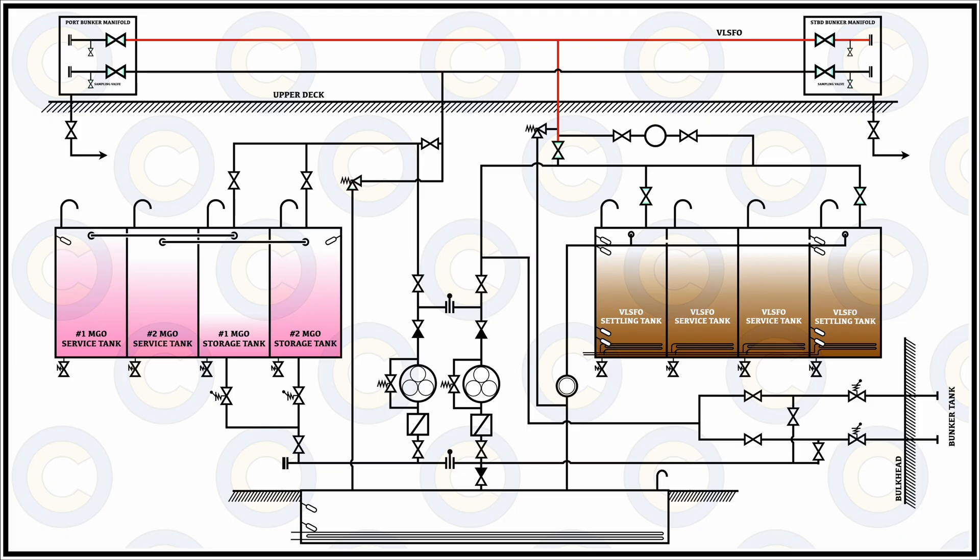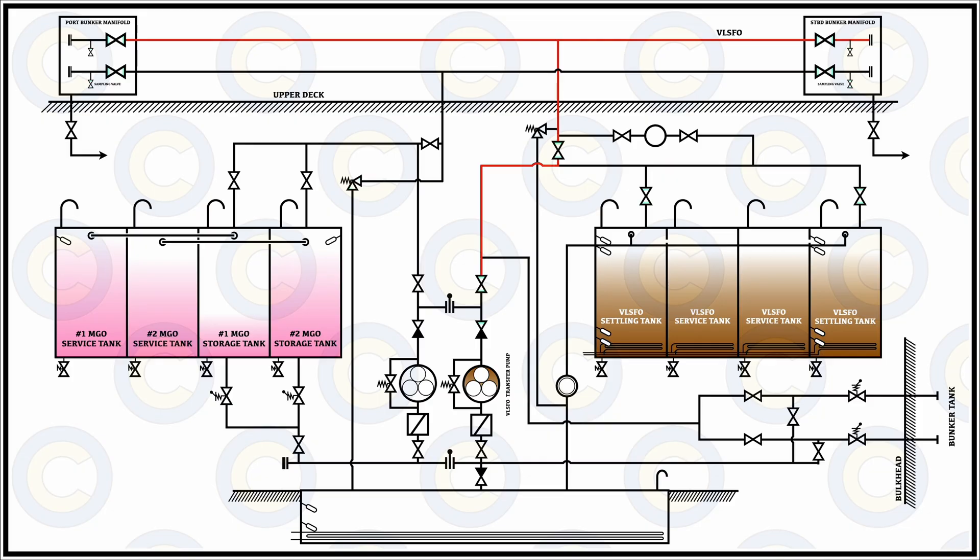Following this trajectory, we would again be making sure that the transfer pump is isolated and so is the interconnection. That is why we have shown the interconnection being blanked, and here is the valve that we want to be closed connecting the transfer line to the bunker line. This valve also remains closed, meaning the oil now has only one access to flow along this line and go and await on the bunker tank filling line.